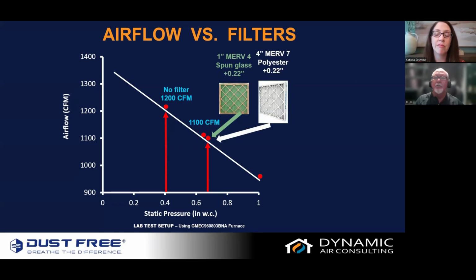So let's go ahead and introduce another one. Here is a 4-inch. So this is a 1-inch, here's a 4-inch MERV 7. It too has a static resistance of 0.22, and we've only lost 100 CFM. We went up 3 percentage points in our MERV rating, but it's also 4 inches thick. Now, this is made out of polyester. Polyester has a pretty nice electrostatic attraction because of what it's made of. As that air goes across it, we get that rubbing of the balloon on the arm and sticking to the wall effect.